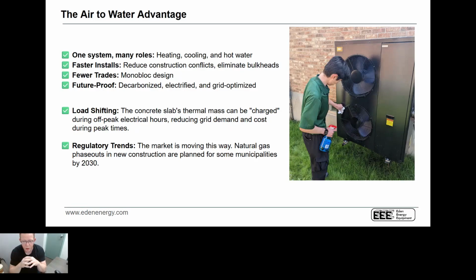And I'm not actually talking just about the air-to-water heat pump. Obviously, with the skilled trades shortage, we want to make sure we have a really, really easy system to install. So when you've got a monoblock heat pump that just needs a water glycol connection from the outdoor to the indoor, that's pretty simple.